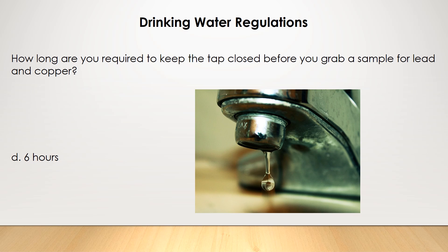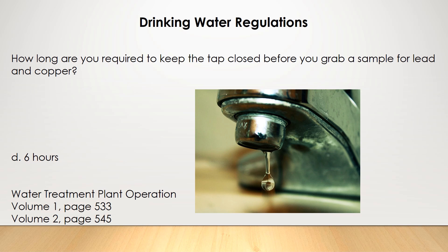Under the lead and copper rule, you're required to let the water sit in the plumbing for at least six hours before you grab a sample. If you want to learn more, go to the textbook Water Treatment Plant Operation Volume 1, page 533. For more on drinking water regulations, go to Volume 2 starting on page 545, where there's an entire chapter dedicated to all the drinking water regulations you'll need to know.